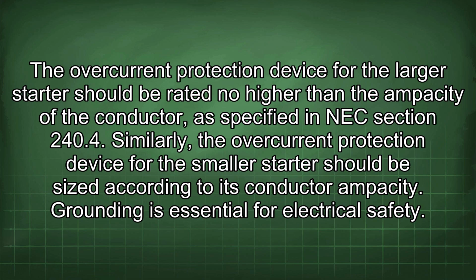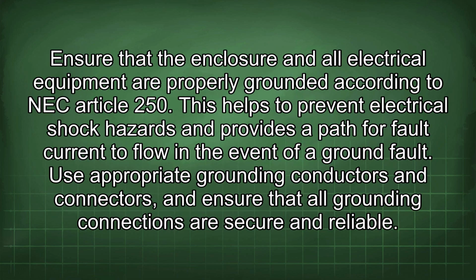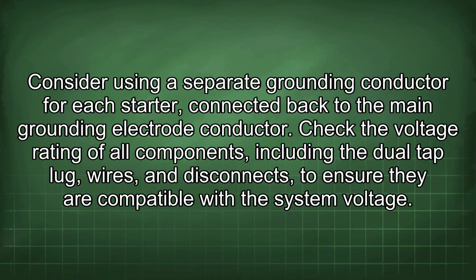Grounding is essential for electrical safety. Ensure that the enclosure and all electrical equipment are properly grounded according to NEC Article 250. This helps to prevent electrical shock hazards and provides a path for fault current to flow in the event of a ground fault. Use appropriate grounding conductors and connectors, and ensure that all grounding connections are secure and reliable. Consider using a separate grounding conductor for each starter, connected back to the main grounding electrode conductor.